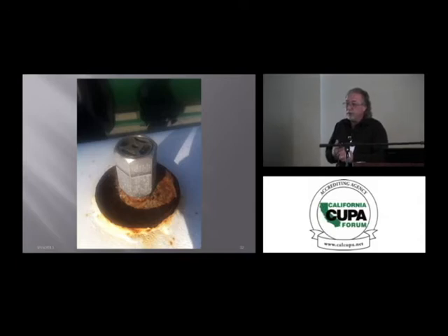Usually the most common place we find a brass fitting is where somebody's gone in there with a test meter. There's certain fittings we can't get for some of these ports except in brass, and they'll use it for testing purposes, but then they'll forget and leave it in. At that plant, they had a bigger challenge. That plant has both Freon, R22, and ammonia. So they have a system that is compatible with brass, and then they have an ammonia system, both in the same engine room, redundant refrigeration systems. And one guy just grabbed the wrong fitting, out of the wrong can, and used it in the wrong place.